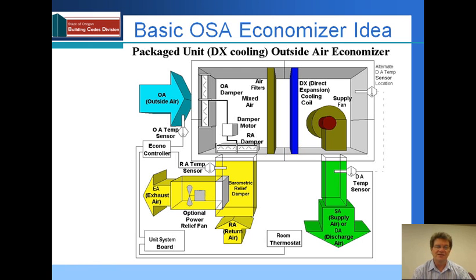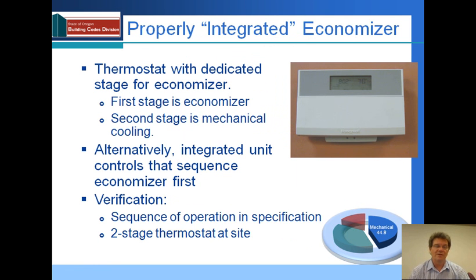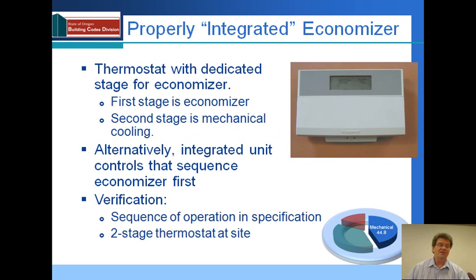In an integrated economizer, it means we operate the outside air economizer partially in conjunction with our cooling coil. In a non-integrated situation, this outside air would be cut off completely when we were above a certain temperature so that only mechanical cooling would be used. One thing that is important for smaller systems for an integrated economizer is to have a two-stage cooling thermostat in the space. The first stage of cooling will operate the economizer when it's available. The second stage of cooling will operate the economizer and the mechanical cooling together. And then when it gets too hot outside, the changeover controls will cut off the economizer.